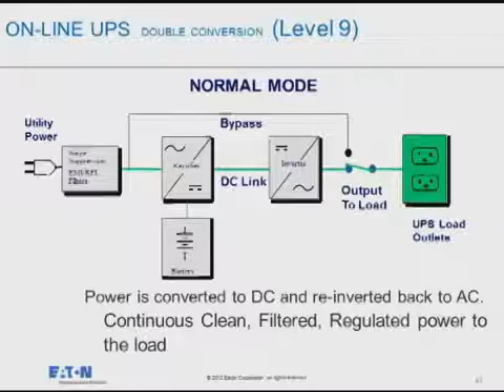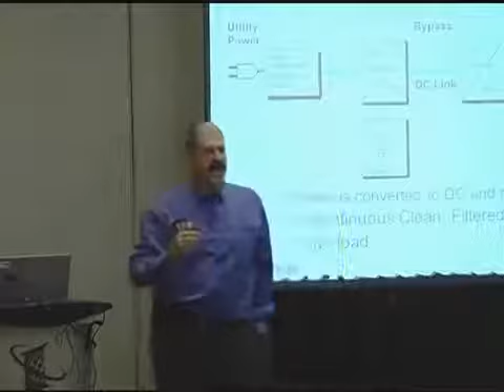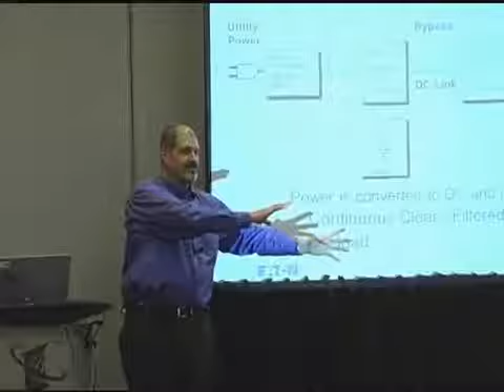So the inverter is also regulating the output voltage THD on a regular basis. Now, in former designs where we're using SCR-based rectifiers on the front end, you ran into instances where this rectifier was creating 34% harmonic currents onto the grid and upstream. Well, two things. At the time, this harmonic current requirement onto the grid was no worse than the harmonic current in the loads. Even though it was high, the technology at the time was still better than your typical loads, than your switch mode power supplies at the load. So it was an improvement.